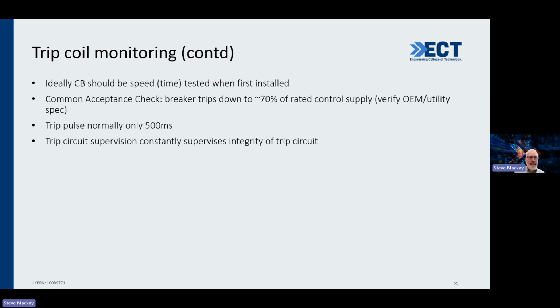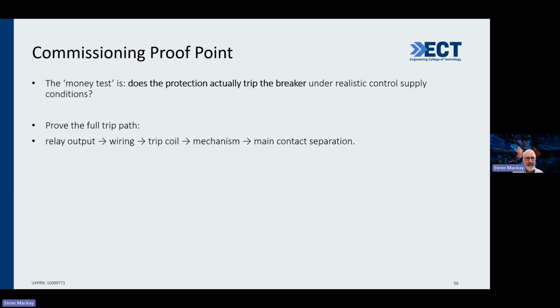And then obviously when you first install your circuit breaker, it should be speed time tested, and it should be about 70% of rated control supply. I'm just giving you a rough figure. And the trip pulse is normally about 500 milliseconds. Trip supervision constantly supervises the integrity of the circuit.